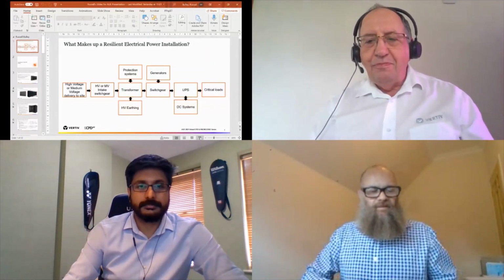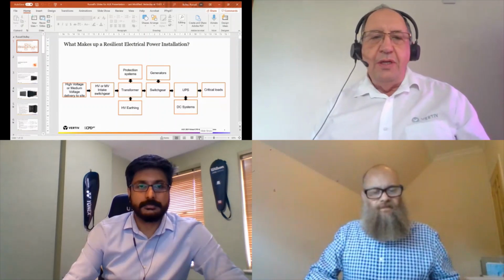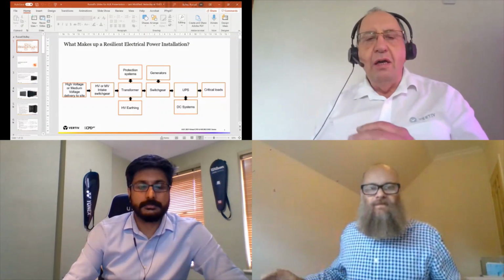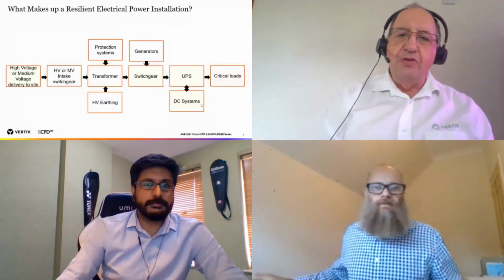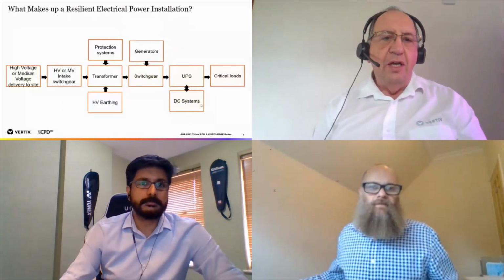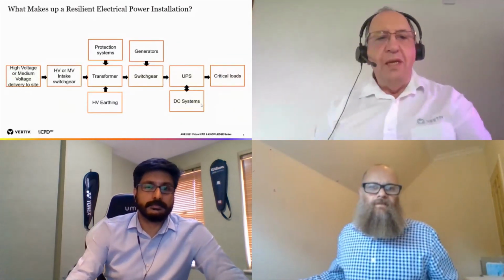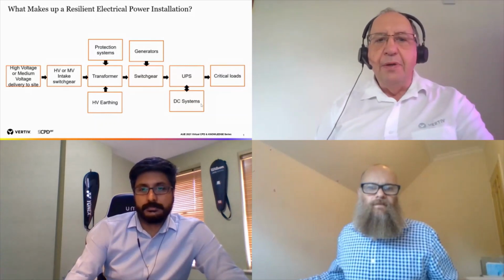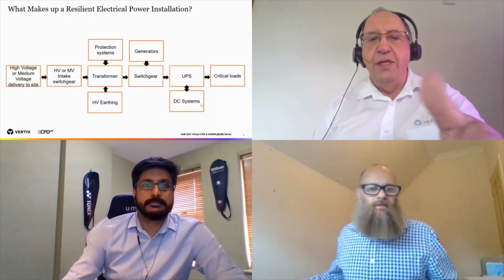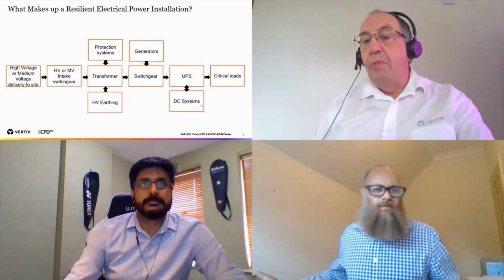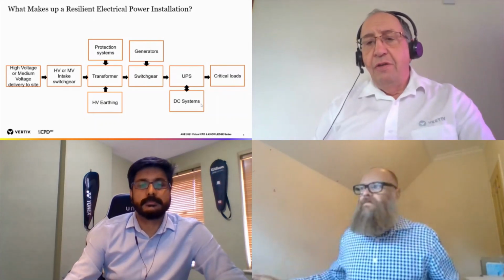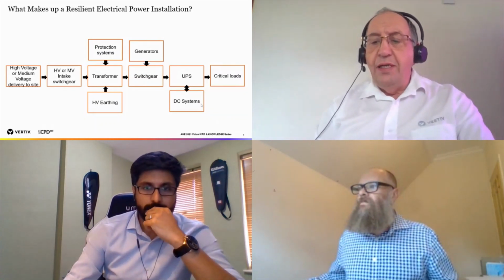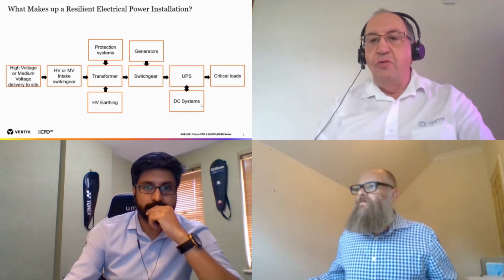Anyway, just so that we can see where we are, where UPSs and batteries sit within a conventional architecture. Obviously, we've got medium or high voltage coming into a campus through a transformer, then some switchgear, where we probably join up with a generator. Then we go to a UPS with a DC system for energy storage, and then critical loads downstream.